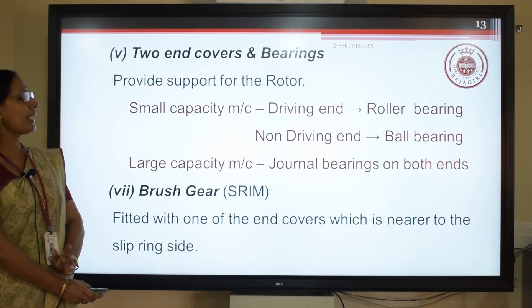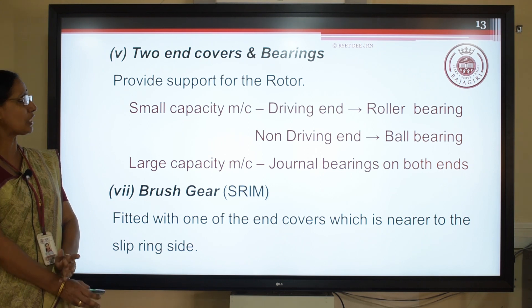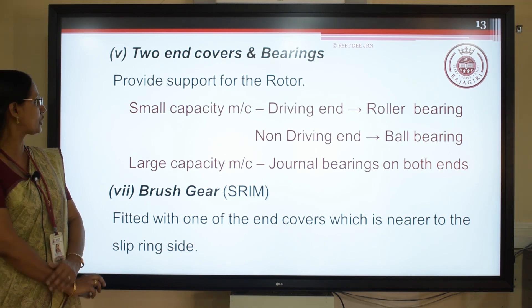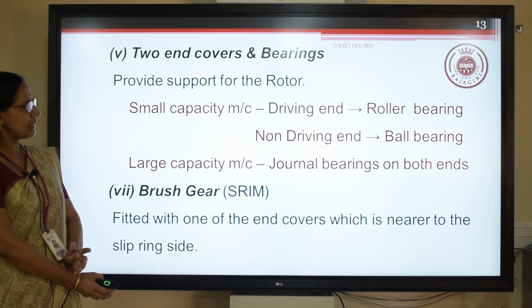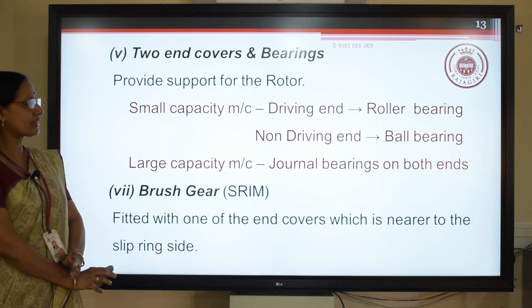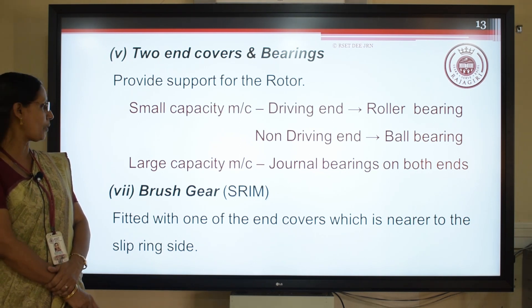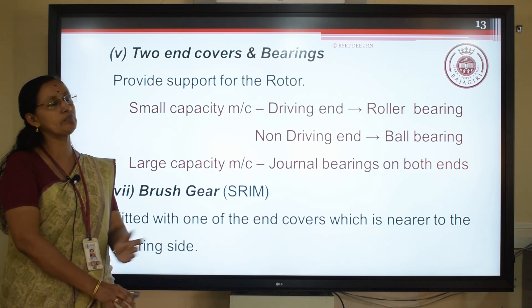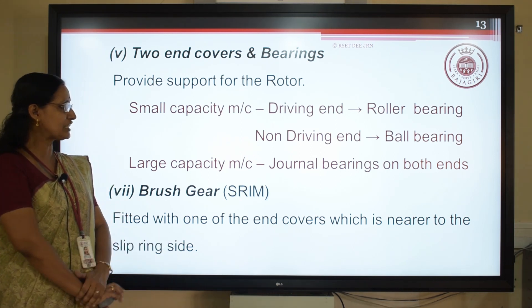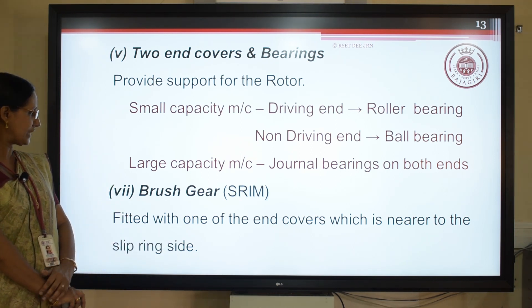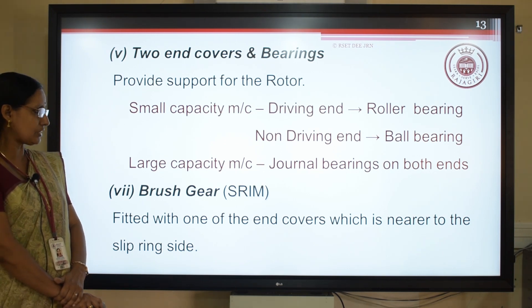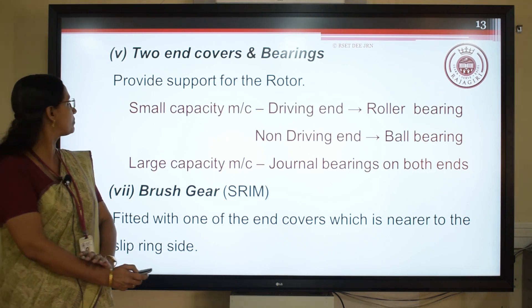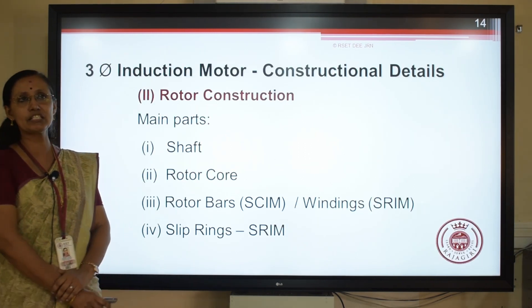The two end covers and bearings, which are part of the stator, provide support for the rotor. For small capacity machines, the driving end uses roller bearings and the non-driving end uses ball bearings. For large capacity machines, both sides are provided with journal bearings. Brush gear is applicable only for slip ring induction motor and is fitted onto one of the end covers nearer to the slip ring side. Those are the parts of the stator.